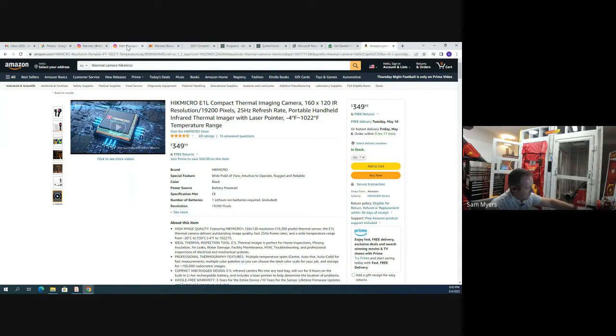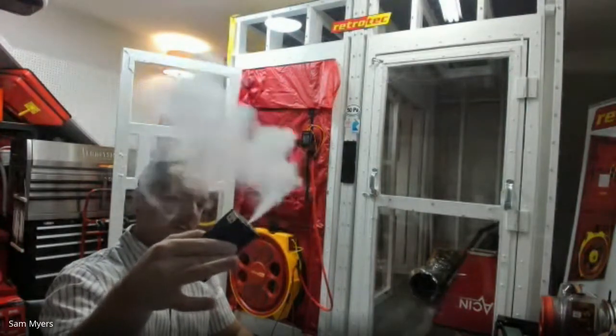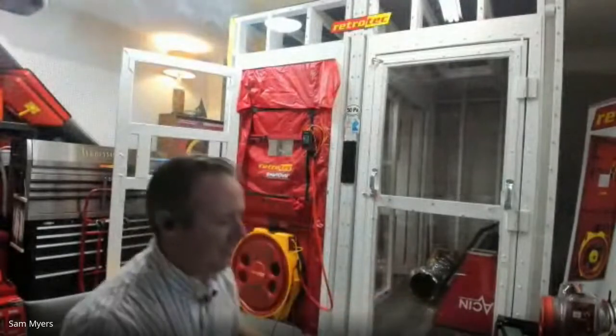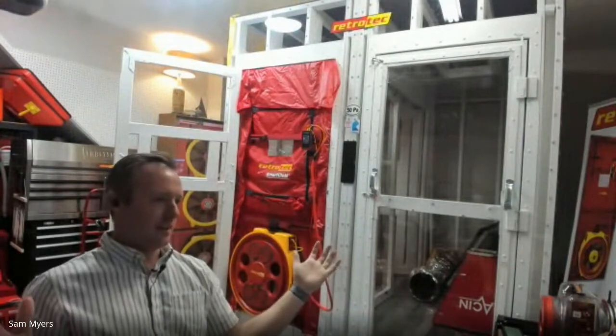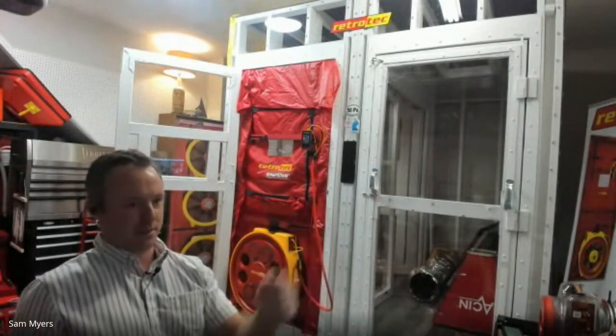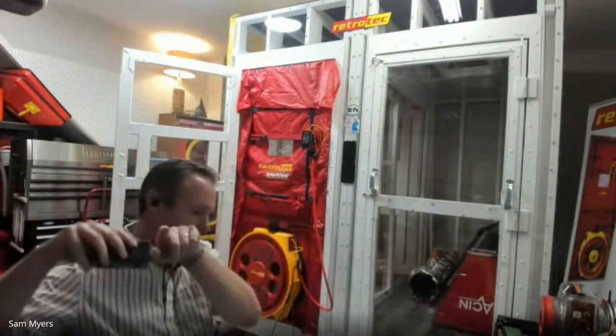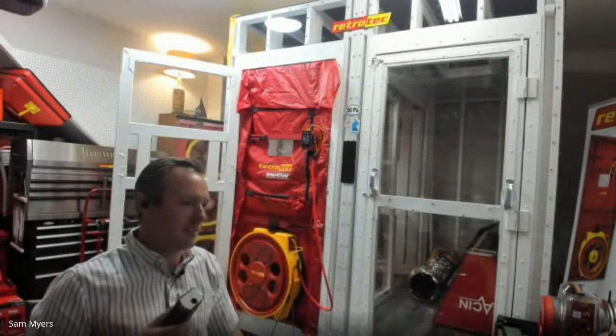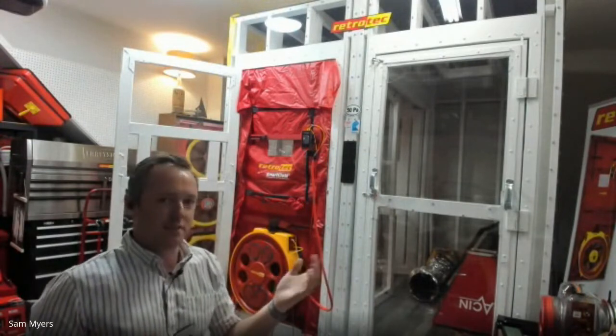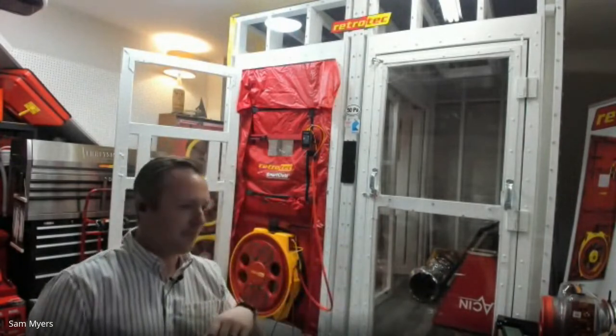Yeah, so that's when I use something like this. It's a handheld smoke machine. Basically, an e-cig in reverse. Party. Yeah, it's a good way to make an entrance too. But what I usually like to do is flip the fan around and then pressurize the house. Then you can go around and shut some bedroom doors, and then discharge that fog near the door undercut. If it gets shot up underneath that door, then you've got some leaks in that room that you want to focus on somewhere. It's such a quick and easy way to find stuff. It just makes that air current visible. It's going to push that air out through the leaks, and so it creates a trail for you to follow.